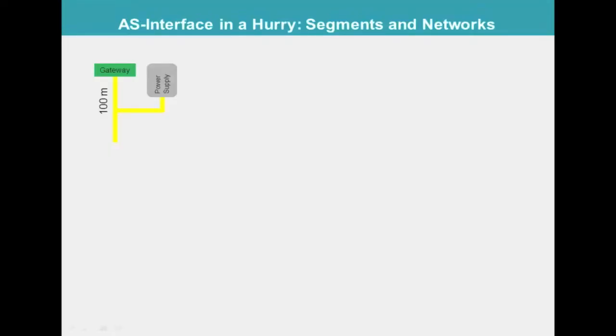Starting at the gateway, a linear AS interface segment can be up to 100 meters long. The segment must be powered using exactly one AS interface power supply.